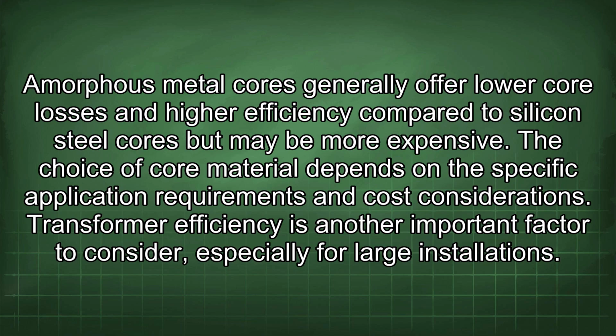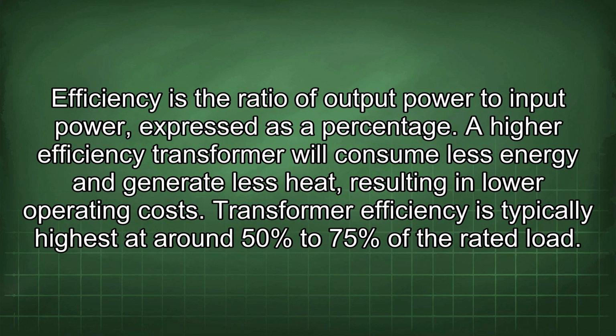Transformer efficiency is another important factor to consider, especially for large installations. Efficiency is the ratio of output power to input power expressed as a percentage. A higher efficiency transformer will consume less energy and generate less heat, resulting in lower operating costs. Transformer efficiency is typically highest at around 50% to 75% of the rated load.